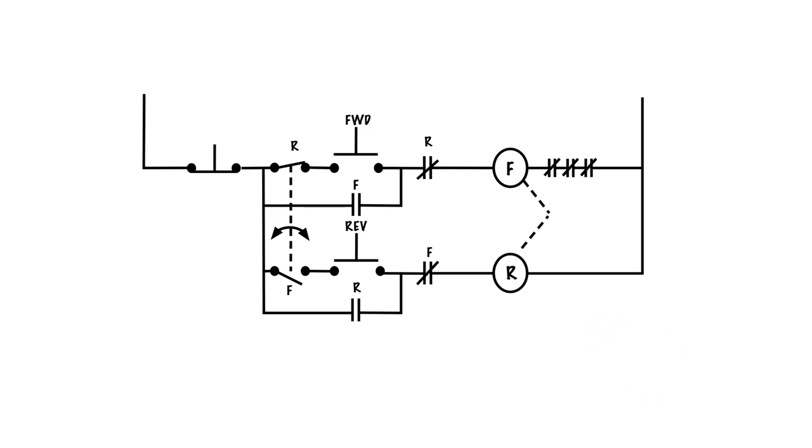Now when I go ahead and hit reverse it will do the exact same thing it did in forward but in the opposite direction. So let's take a look at how this whole sequence works. I push down the reverse button, the R coil energizes, our contacts close, holds in our contact, interlock opens up, the motor starts to spin in the reverse direction.